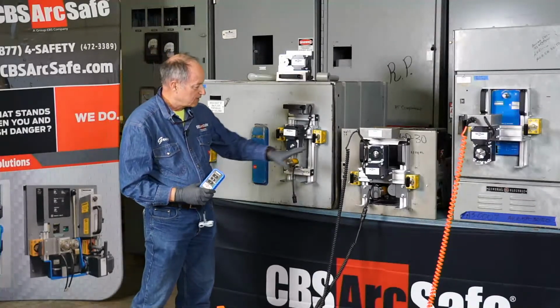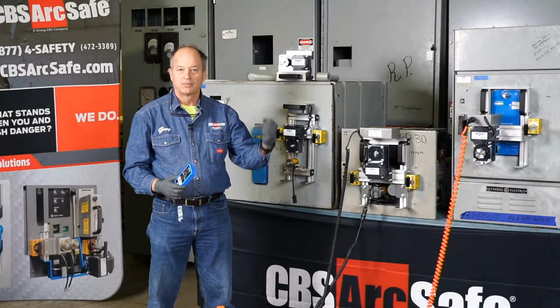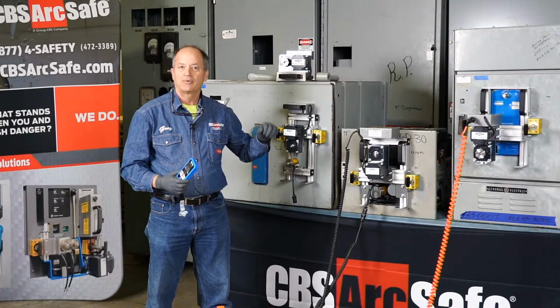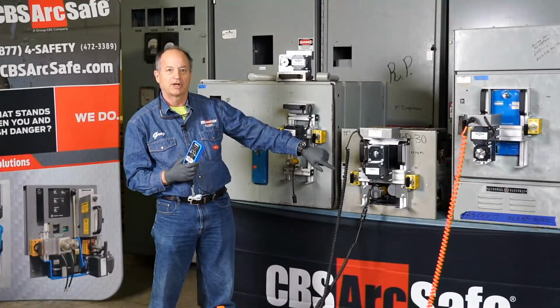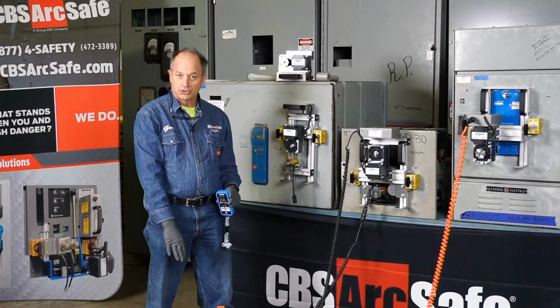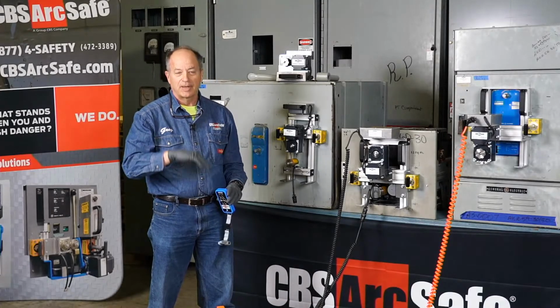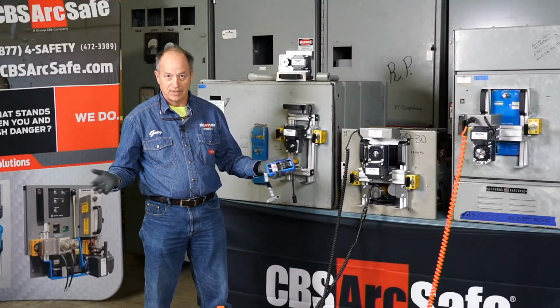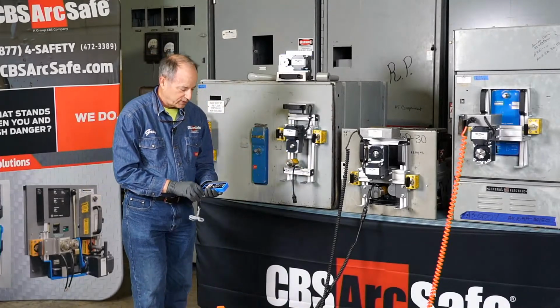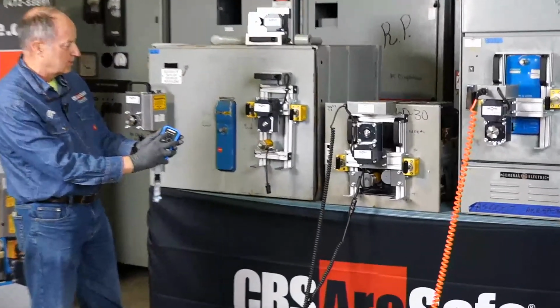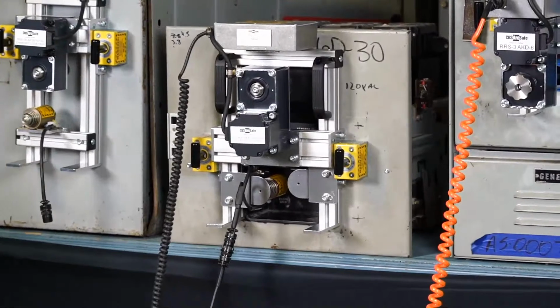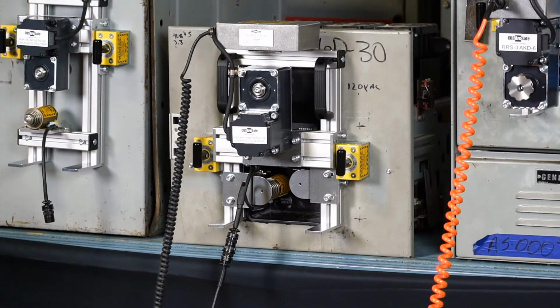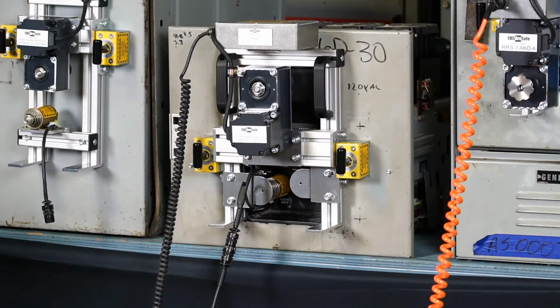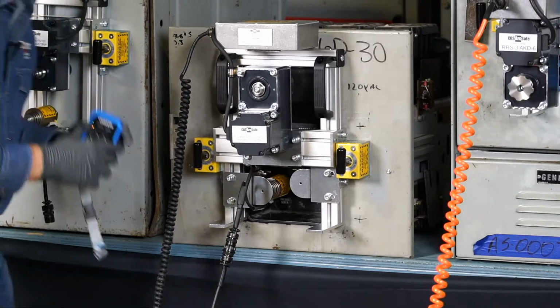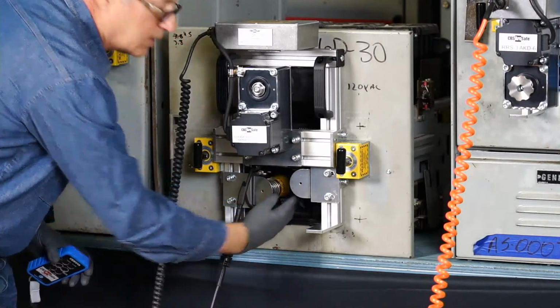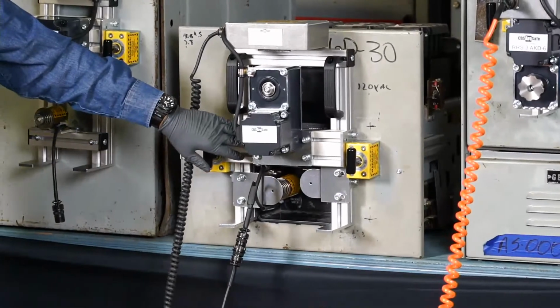And then you have other breakers like this one, where we're going to charge the spring with 1 to 3 to 5 different strokes. And then we have to push on a button to close it and push on another button to trip it. So if you wonder why it says charge close, we had to figure out what to name this about 12 years ago, and this is what we came up with for a nomenclature for this. So at this point, we would hit our charge close button once. Now we've got our spring charged, and if we were actually able to look inside here, we would see that it has a yellow label here that does say charged way down deep inside of this, okay?